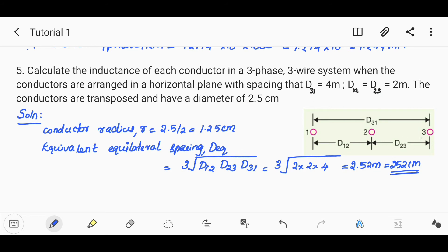For the horizontal plane arrangement, the conductor diameter is 2.5 cm, so the radius is 2.5/2 = 1.25 cm. The equivalent equilateral spacing D_eq equals the cube root of D12, D23, D31, which gives 252 cm.